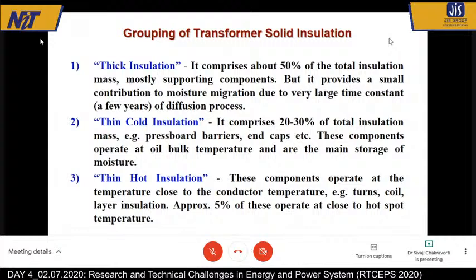to 30% of the mass, called thin but cold insulation. Thin because these are mostly the end caps, the small barriers between the discs, etc. The important part is they operate at the bulk oil temperature. Now, the transformers are quite big, so there is something called bulk oil temperature and something called the hotspot temperature. These hotspot temperatures are very close to the windings.